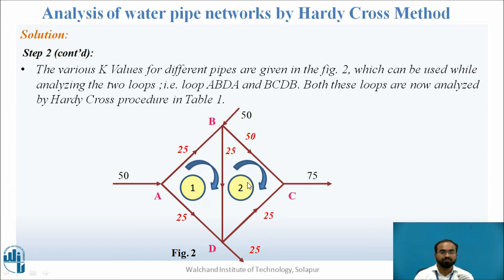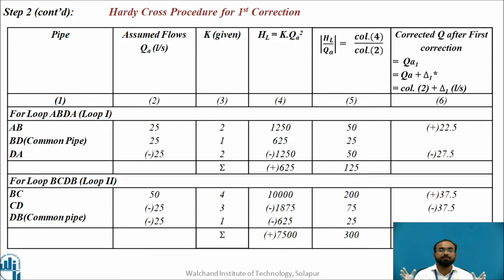Flow rates rotating clockwise will be positive. So for loop 1, A-B is clockwise so it is plus 25, B-D is plus 25, but A-D is minus 25 because it is anticlockwise. The same applies for loop 2. Clockwise means positive, anticlockwise means negative. Now I form a table. Column 1 has pipeline names — for loop 1: A-B, B-D, D-A (where B-D is the common pipe); for loop 2: B-C, C-D, D-B. Column 2 has the assumed flow rates with signs.